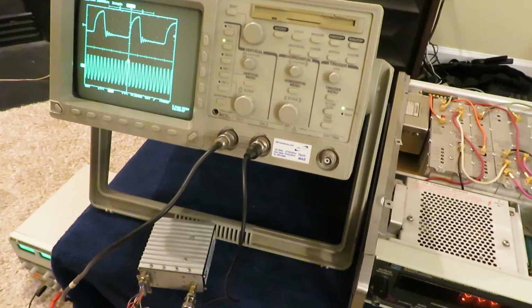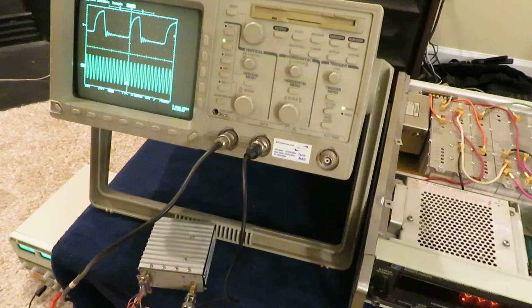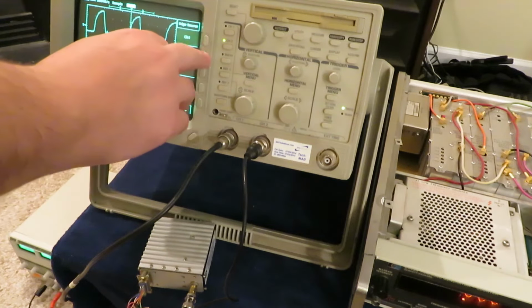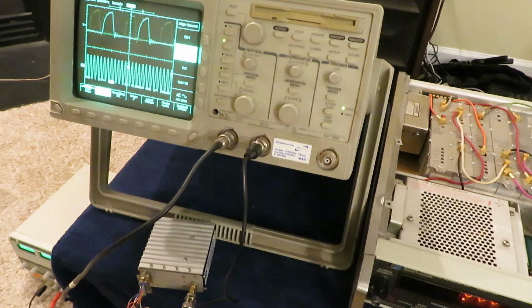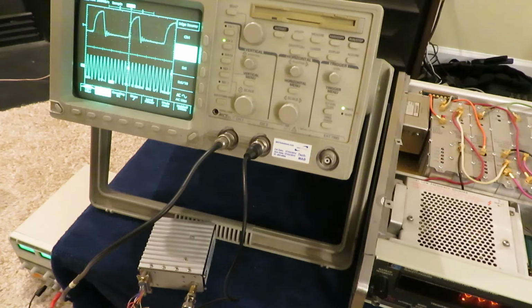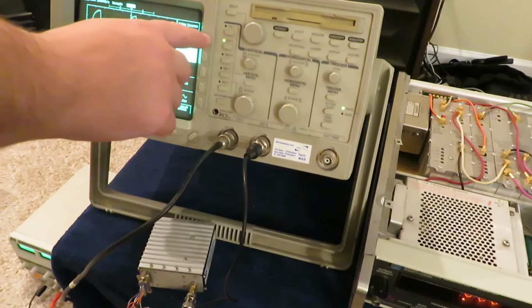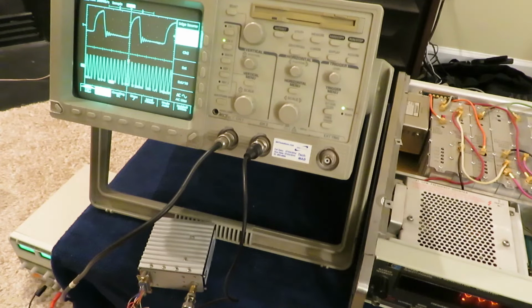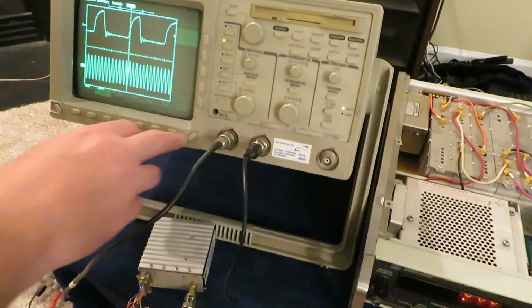The manual recommends you use a 1 megahertz reference to measure the beat frequency against. All I have is a 10 megahertz reference, but we can still make that work. Notably, you're going to want to have the oscilloscope triggering off of the lower frequency of the two, so the 1 megahertz waveform here, because if you have it triggering on the 10 megahertz reference, it's going to be jumping all over the place because it might not be triggering off of the same cycle relative to this one. So you want to have it triggering off of the lower frequency of the two. Just thought I would mention that.